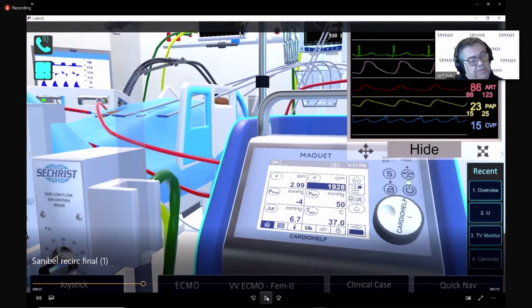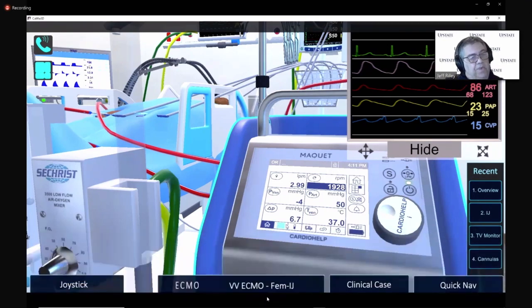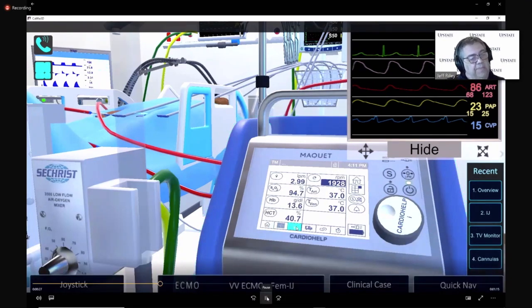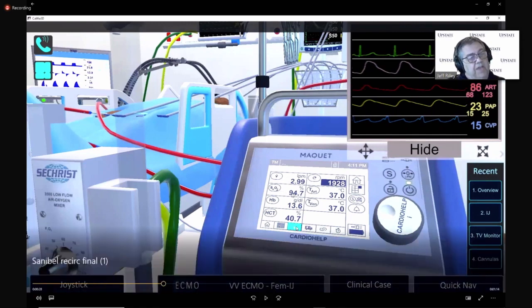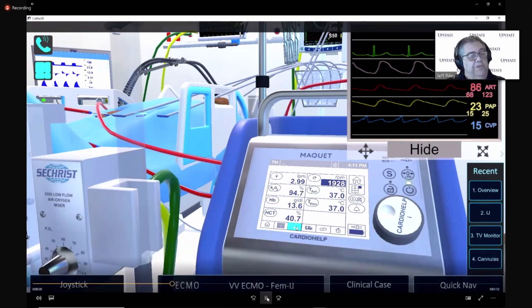But as we continue to look around, the one thing that has caught everybody's attention is the pre-oxygenator sat, or the SVO2 on the Cardiohelp, is up to 95%. And you can see that both blood lines are red. And that is a clue in VV that we're recirculating, as well as the depressed or an unacceptable pulse oximeter value. So we're starting to build a story here that we have recirculation, and we've confirmed the recirculation.